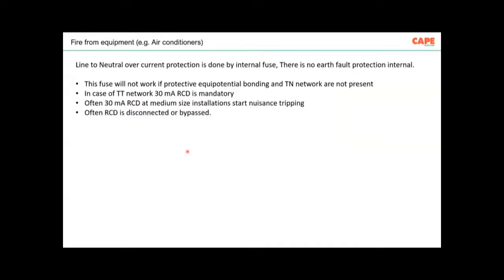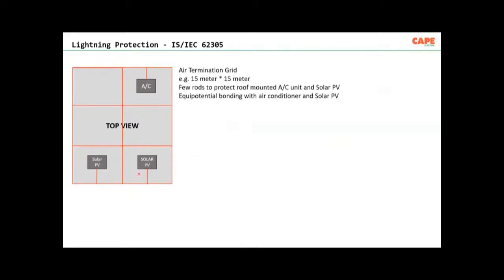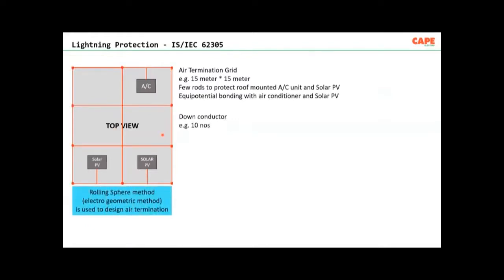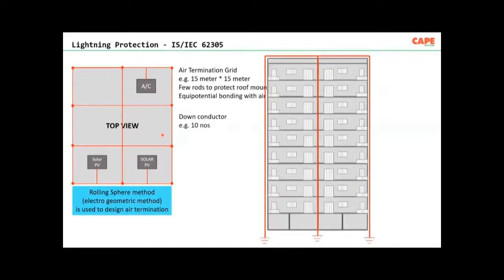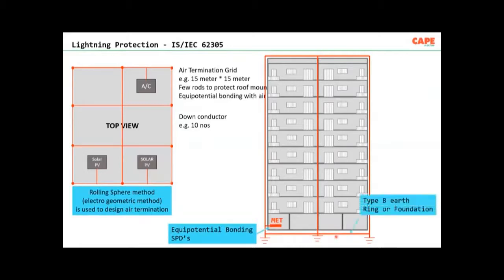So basically, this is all about earthing. One of the main applications of earthing which we discuss is lightning protection. What do we mean by lightning protection? You know very well that lightning protection, the standard 62305, advocates a mesh at the top of the building. Then several down conductors, for example, 10 down conductors in a typical building. Then equipotential bonding, that means the down conductor and the MET are connected together. Then you can have earth electrodes in soil or earth electrodes inside your concrete and so on.